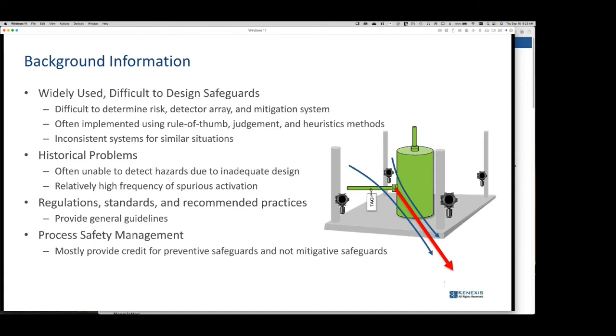I just had a call from a company down in Texas somewhere, and they were having the same problem. The guy's like, "Hey, certain times of day on certain types of weather, our fire detectors are going into alarm." And I'm like, "Yeah, it's a brand new site, right?" He goes, "Yeah, all brand new equipment, shiny, beautiful, beautiful process, beautiful metal." And I went, "Yeah, I know." And I said, when the sun gets to the right angle, it's reflecting, and you have IR detectors that are detecting the actual reflection as a heat source. But the problem is that we make really bad decisions.